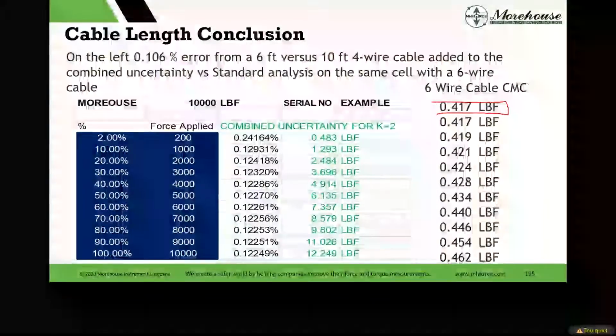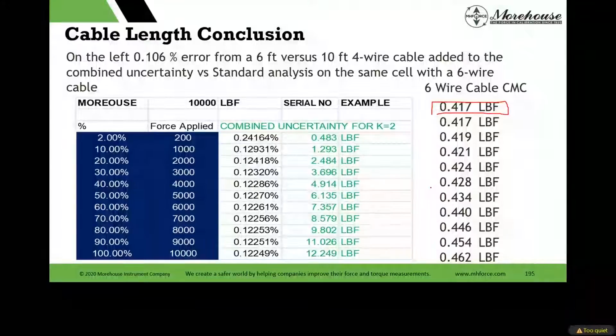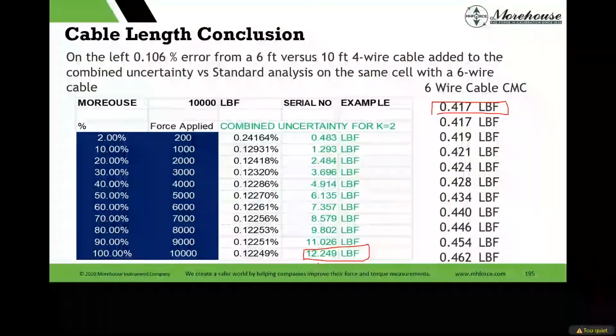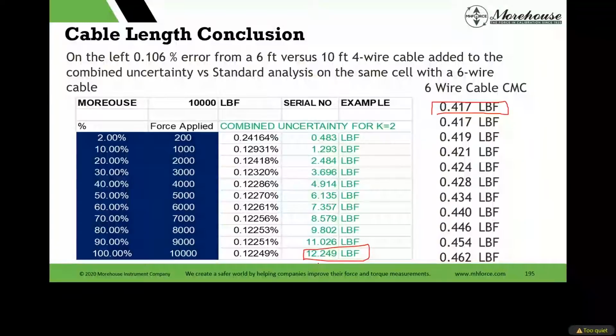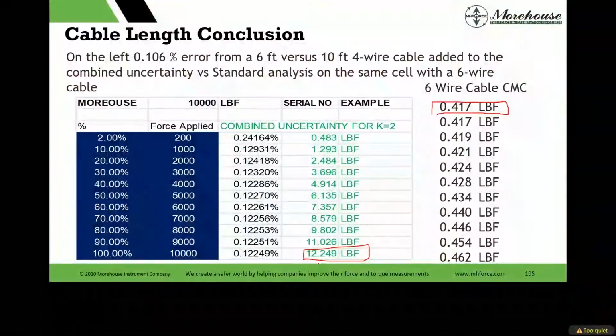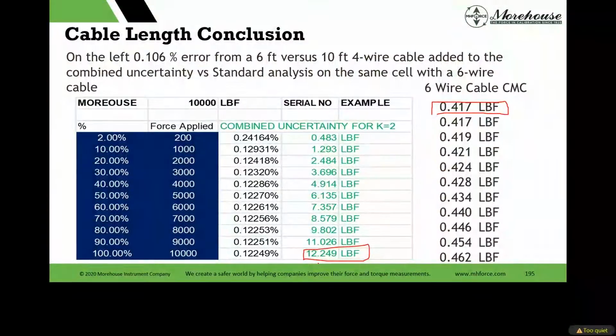And then I typed this in an uncertainty sheet and showed people that a cell going out the door where the expected performance is about 0.45 pounds became 12 rather quickly. So sense is a big deal in that aspect of swapping cables. It certainly ruined the one customer's stability year to year. We try to work with them and say just serial number your cable and keep them. If you use the long cable for everything, they didn't want to do that, so they continually have problems.